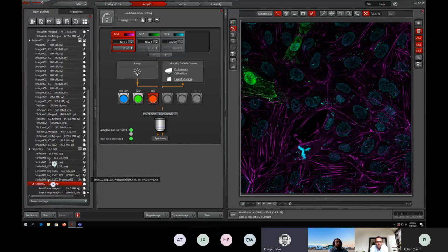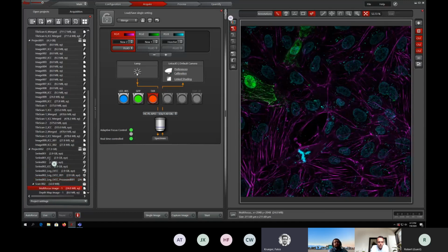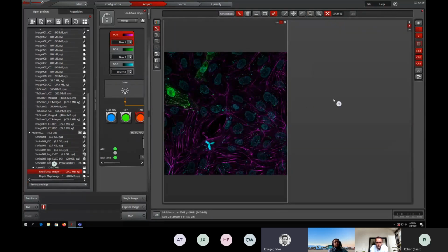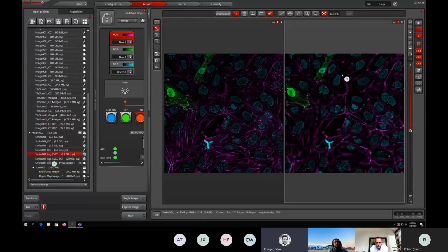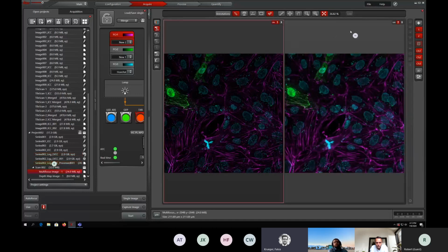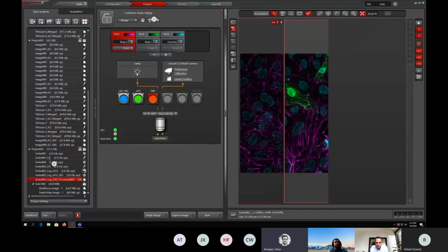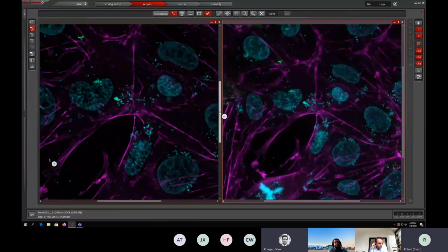Maybe just coming back to this processing again. So this one here was the maximum intensity projection. And now if we have a better reference channel, so I use now the DAPI channel for the extended depth of focus, this is what we create. Here, I think it's even better than the maximum projection. But of course, you are superimposing layers of focus that were never in focus. So this one has to keep in mind. Left-hand side is the maximum intensity projection. Sorry, the extended depth of field.